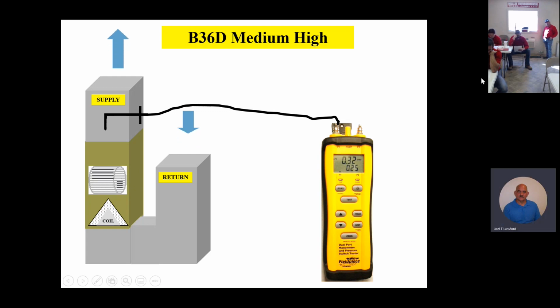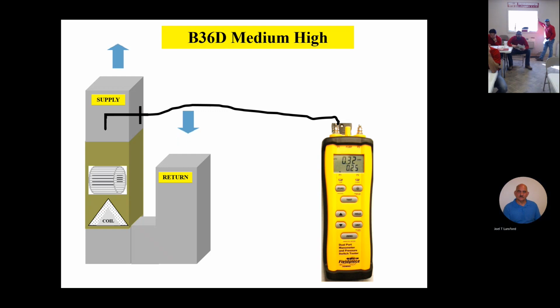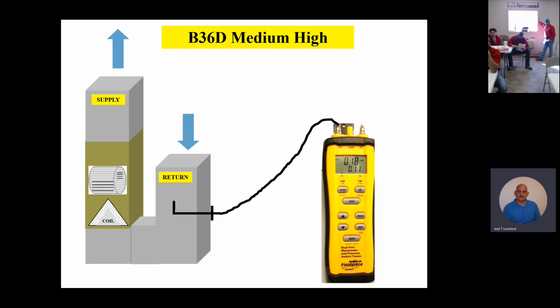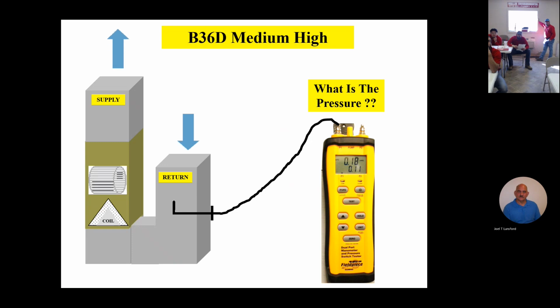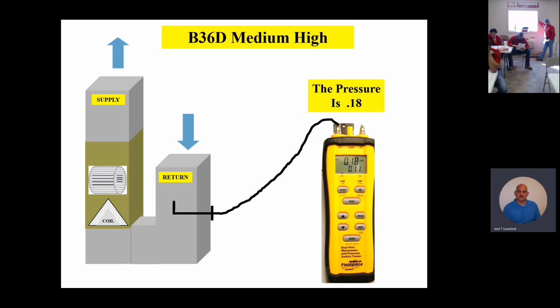And so on your JHET air handler chart, find the B36D model. It's on medium high speed tap. So find B36D, medium high speed tap, and our supply static pressure, you said it was a 0.32, so write that down and remember it. Okay. And then we're going to take our return air static pressure. And that looks like it's about a 0.18. So 0.32 plus 0.18 equals what?